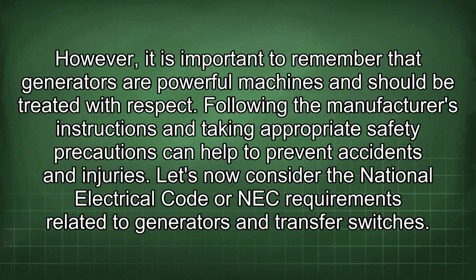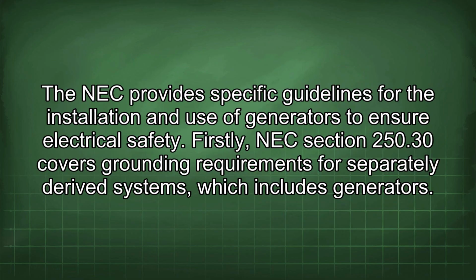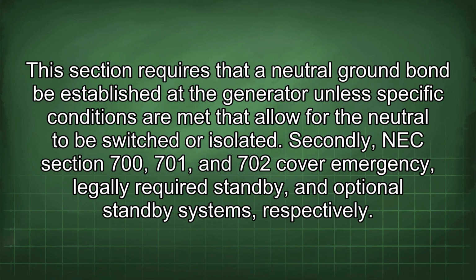Let's now consider the National Electrical Code or NEC requirements related to generators and transfer switches. The NEC provides specific guidelines for the installation and use of generators to ensure electrical safety. Firstly, NEC Section 250.30 covers grounding requirements for separately derived systems, which includes generators. This section requires that a neutral ground bond be established at the generator unless specific conditions are met that allow for the neutral to be switched or isolated.